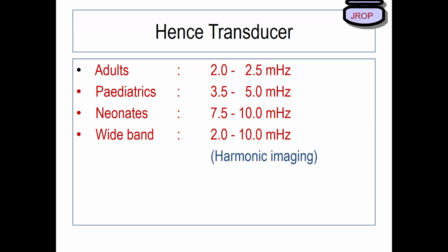at 2 megahertz it's scanning the distant part, with good Doppler study and good penetration. At 4 megahertz, it's scanning the nearer parts, so the resolution of images goes up dramatically. So all in one is a harmonic imaging transducer, and this is what has stayed in today's practice. If somebody is trying to sell you a non-harmonic transducer, they are trying to sell you a DOS-era system in the era of i3, i7, i9.